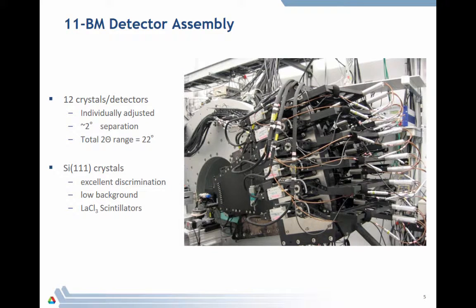A lot of earlier high-resolution diffraction cameras used a single detector. Before I was here at the APS, I was at the NSLS working with Peter Stephens there, and we ran a high-resolution instrument using a single-point detector. Average scan times if you wanted a really good scan would be something in the order of 8 to 10 hours or more. So you'd be looking at a few samples a day at best. We take advantage here, instead of having one detector, we have a bank of 12 detectors all 2 degrees apart, giving a total 2θ range of 22 degrees.